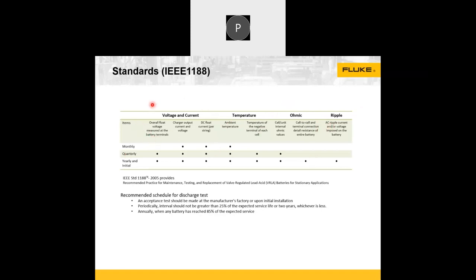You can see in voltage and current also, overall float voltage and charger output and current voltage. Current and voltage are required to be tested in the charger output, and the overall float voltage of your battery system needs to be tested, and DC float current also needs to be tested, because this is the string current or overall current taken from the system. This is also possible with our battery tester, because it comes with a clamp for measuring DC current. And then the temperature.